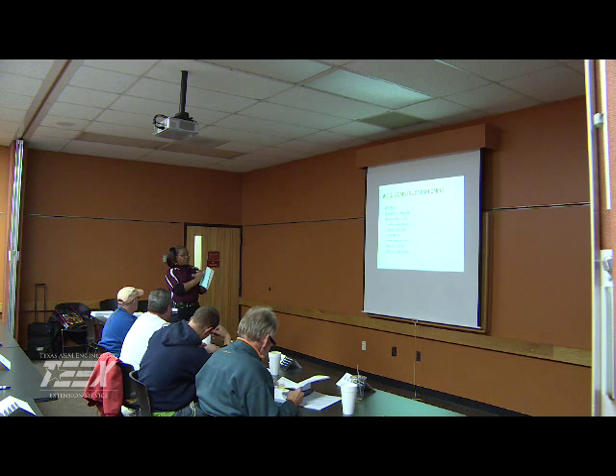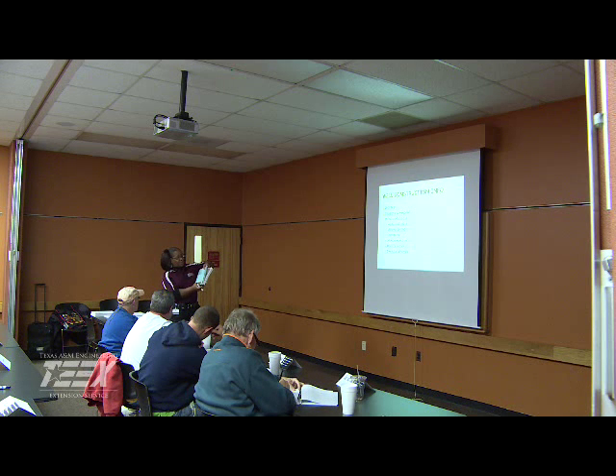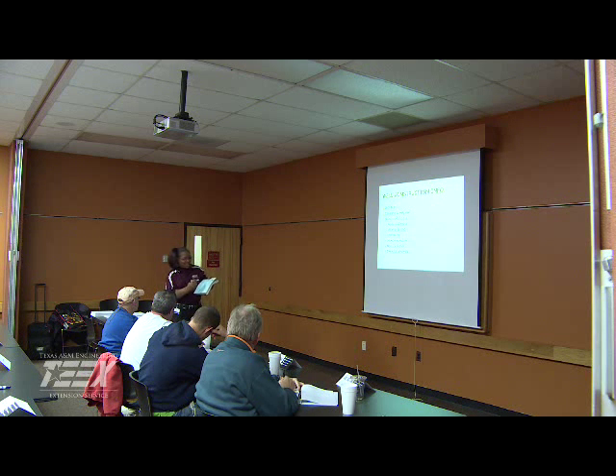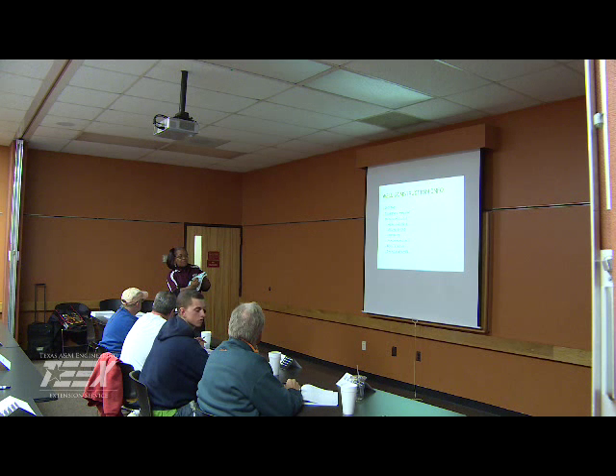So what we're looking at is motor horsepower, and this is my big chart here, I do apologize. We have gallons per minute times feet of head. I'm just going to put head because of my limited space, but that's head in feet. If you have PSI, how do I convert that to feet? 2.31, utilize that. Divided by a constant, 3960, times pump efficiency, in percent, changed to a decimal, times motor efficiency.